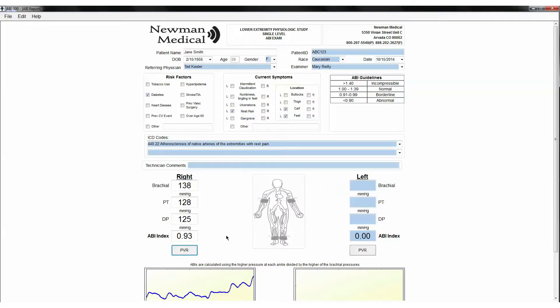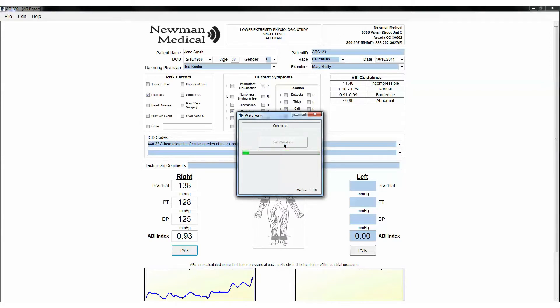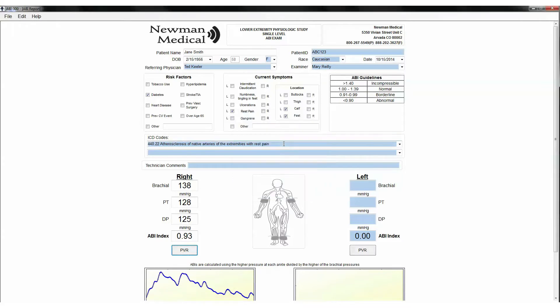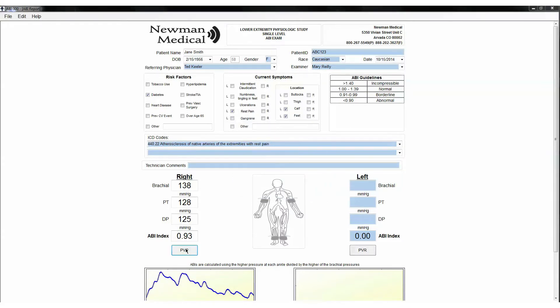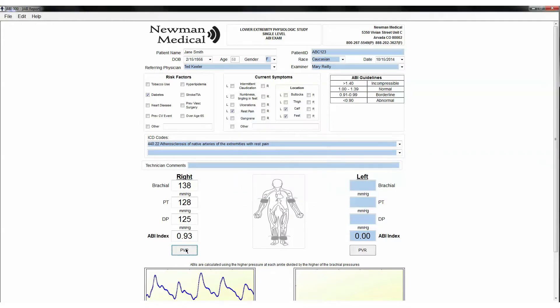The bar being in the middle is 65 mm and the recommended pressure to take the PVR waveform. Please note, you may take a PVR waveform as long as the bar is neither completely empty nor completely full. It is not necessary for the pressure to be exactly 65 mm. Press the Get waveform button to take 5 seconds of data. If you want, you may repeat to collect 5 seconds of data. It will overwrite the previous waveform.